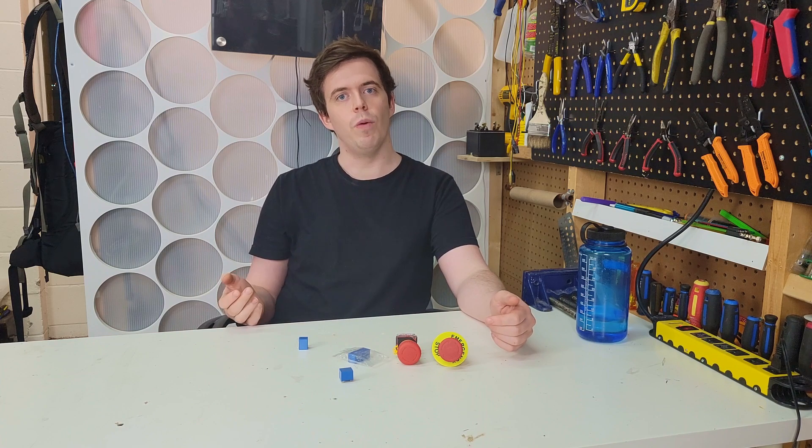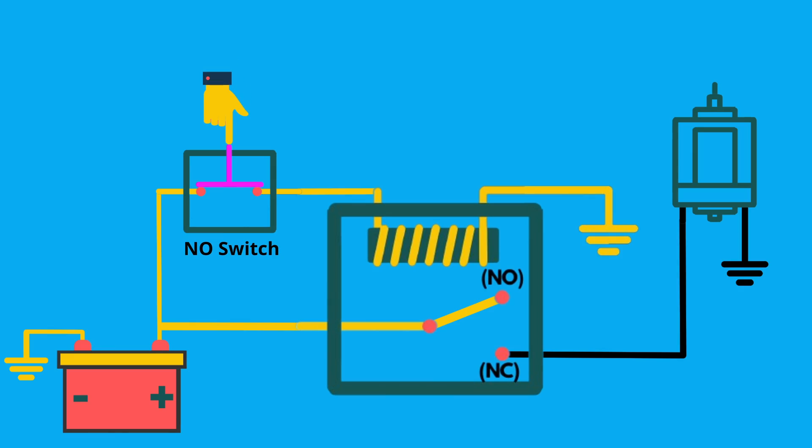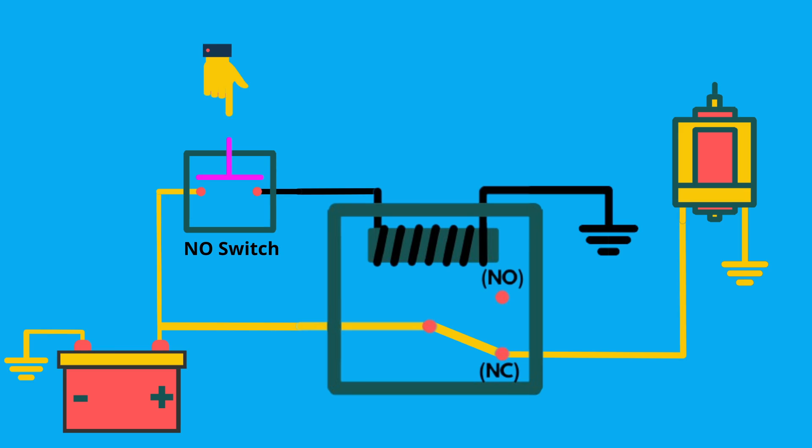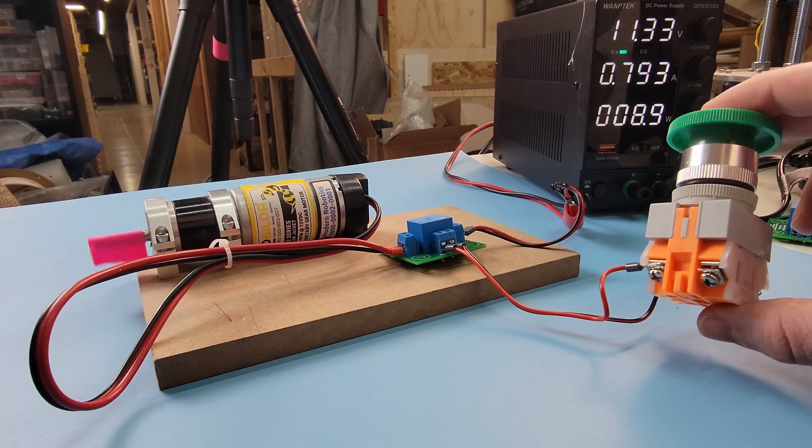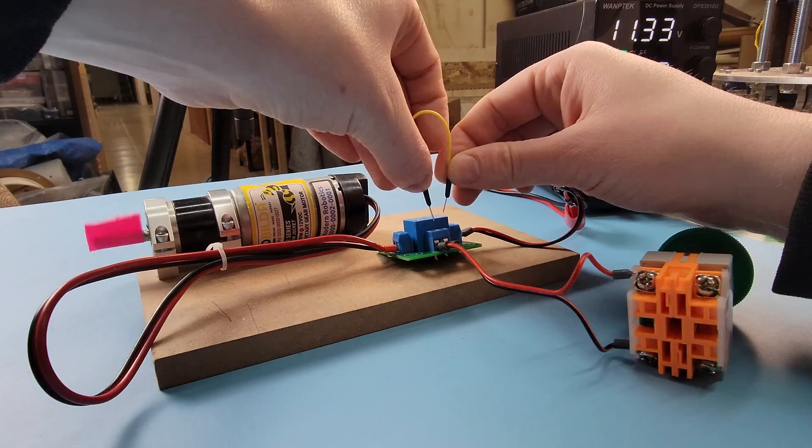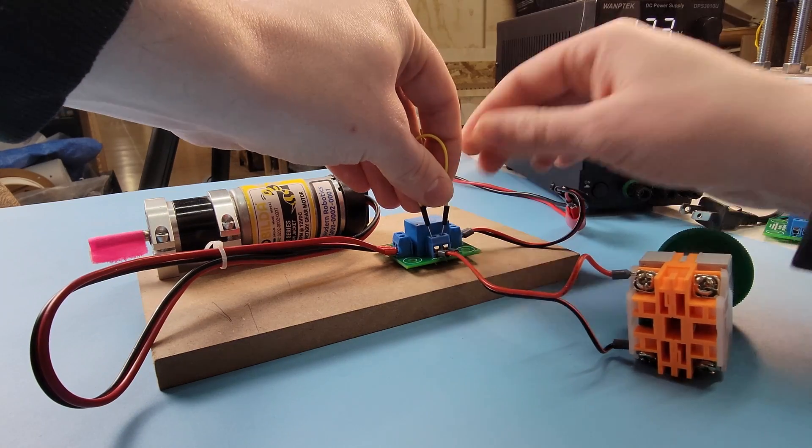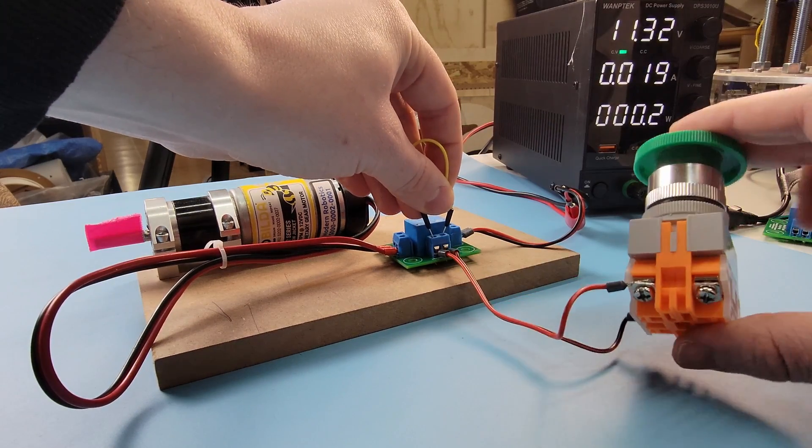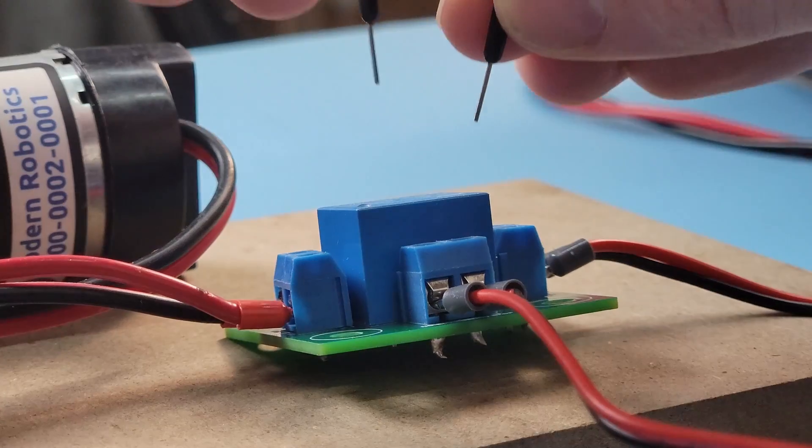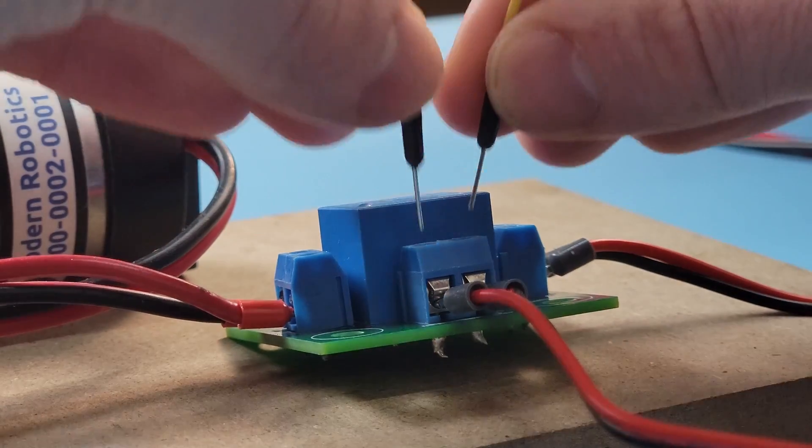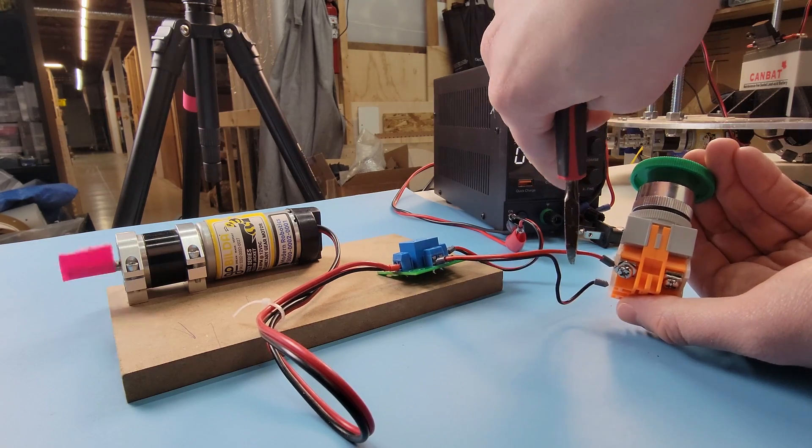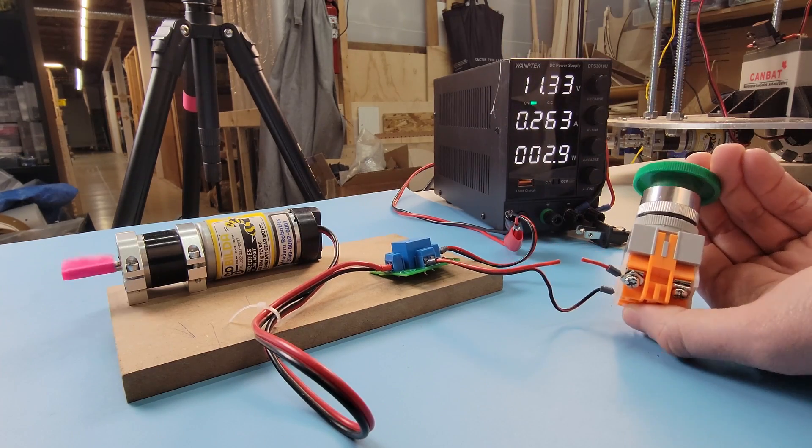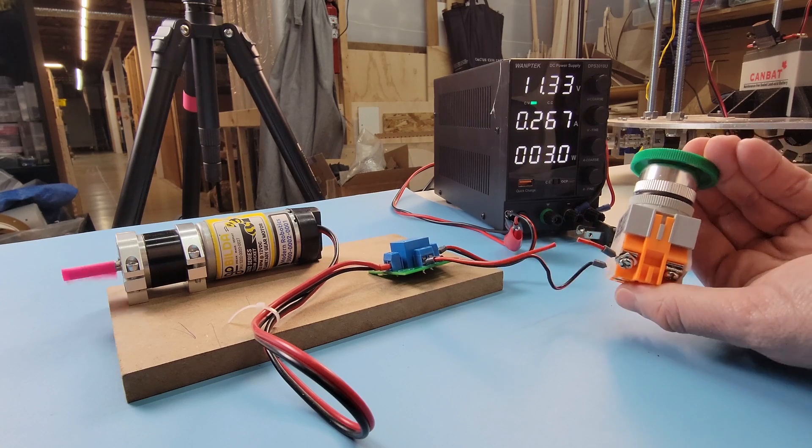Let's try with a normally open one. I'll wire it up with a slightly different relay configuration. And sure enough, it works when the emergency stop button is hit. In the event of a short circuit, it fails in a safe manner. That is to say, it cuts power to the motor. This looks good. However, if there's a break in the connection, then the switch will fail in an unsafe way, as the motor can still run even when the button is hit.